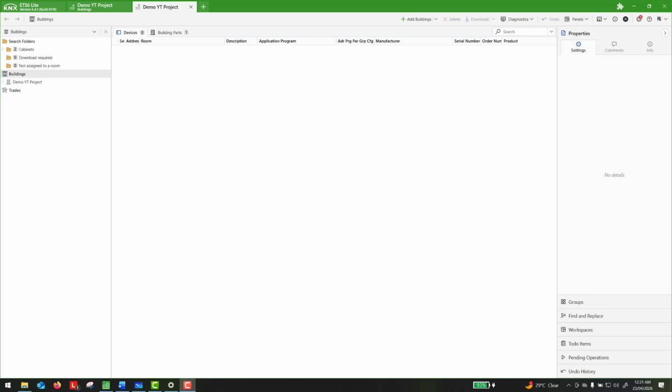And in this video, we are going to see the KNX topology. I know that in my previous video, before I was ending it, I mentioned that we'll be seeing how to add the devices into the project, right? But here, before adding the devices to the project, we need to actually understand how the devices will be connected with the physical KNX TP medium, that is the KNX cable, the green colored cable that everyone knows, right? So to understand how these devices are connected in the bus, we need to understand how a topology is made.